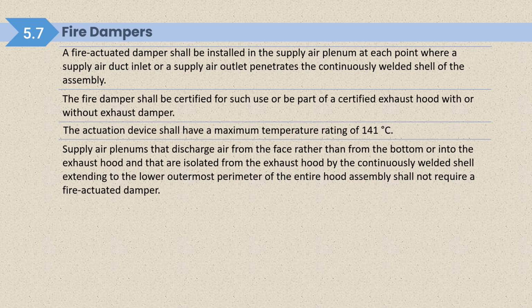Supply air plenums that discharge air from the face rather than from the bottom or into the exhaust hood, and that are isolated from the exhaust hood by a continuously welded shell extending to the lower outermost perimeter of the entire hood assembly, shall not require a fire actuated damper.